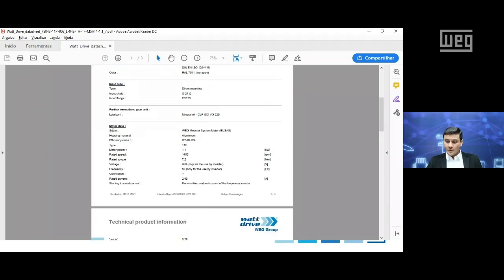So the data sheet of the complete geared solution looks like this. Here you are going to have the gear data that you have input: the output speed as we input since the beginning, the number of stages of this gear, the color, the dimensions, and so on. You are also going to get the motor data, the motor that we selected, in this case 1.1 kilowatt, the rated speed of this motor, a 4-pole machine, torques, the rated current as informed in the software during our selection, and the certifications for these motors.